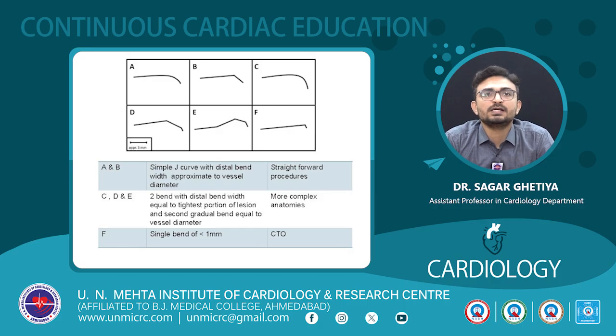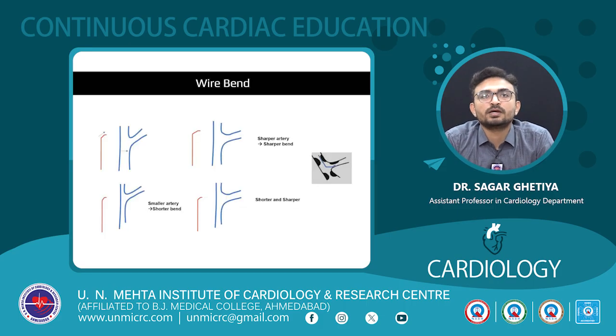While in figures C, D and E, we have a two-bend tip where the distal bend is equal to the tightest portion of the lesion and the second gradual bend is equal to the vessel diameter. It is used in more complex anatomies. While in figure F, there is a simple bend less than 1 mm from the distal tip, which is used in CTO. So this figure helps to visualize the bends.